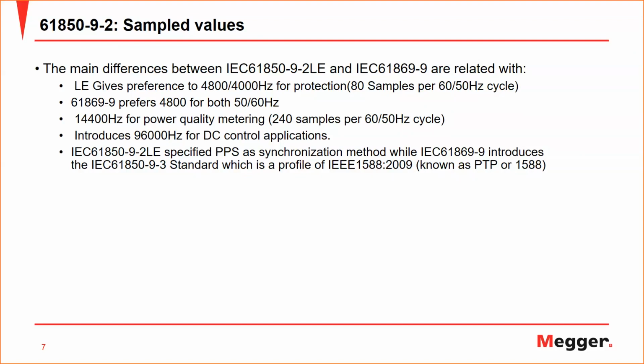And as well, the 61869-9 introduces different sampling frequencies for different applications, like power quality metering and also DC control applications. It also introduced a new time synchronization method, where the light edition only added PPS, which stands for pulse per second synchronization method, while the 61869 added a new profile, which then became -9-3.